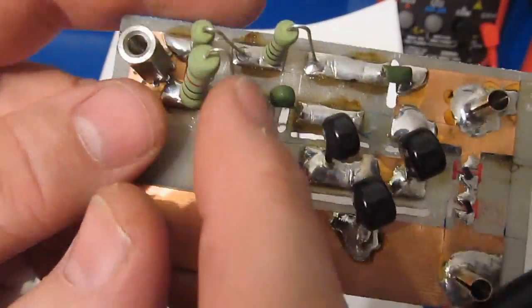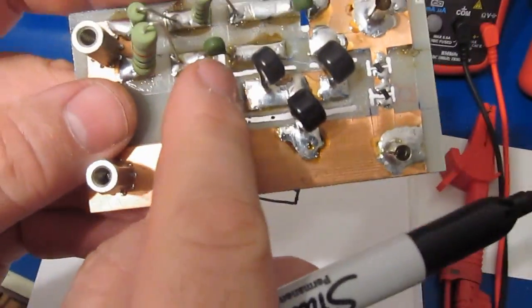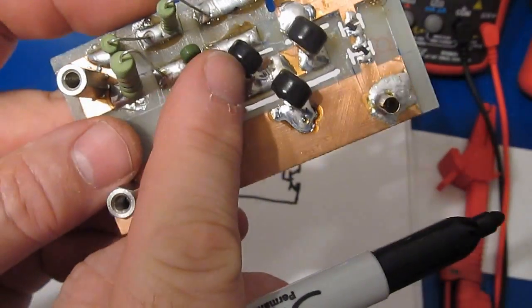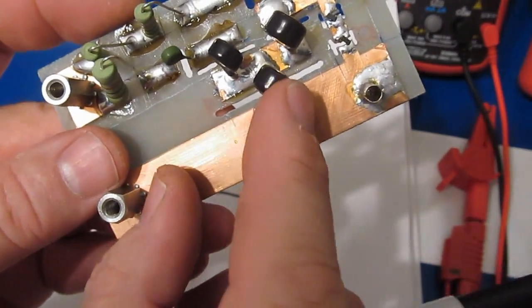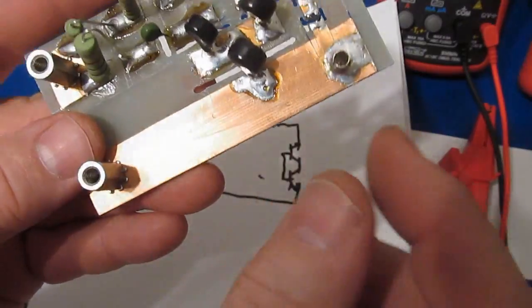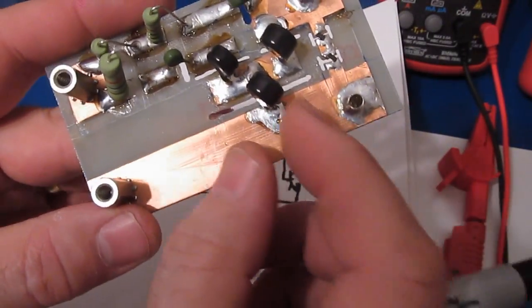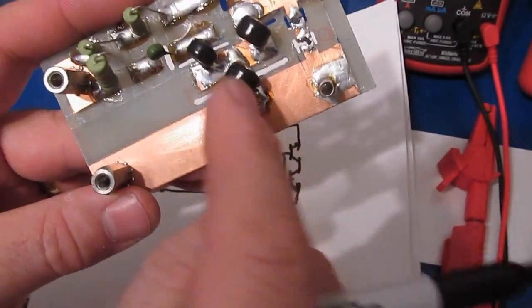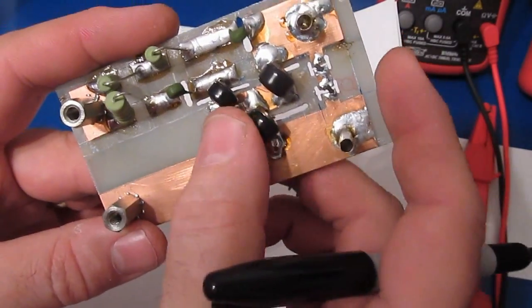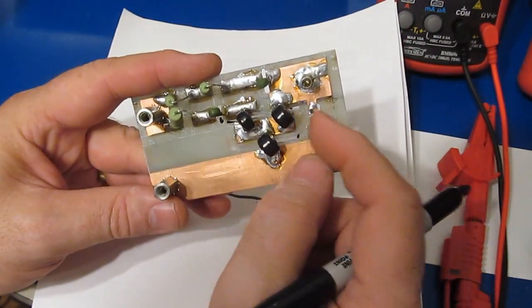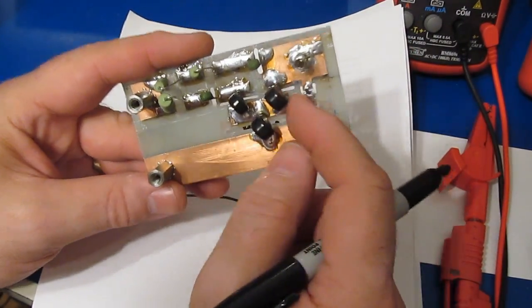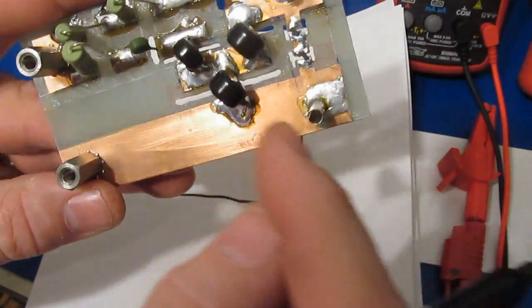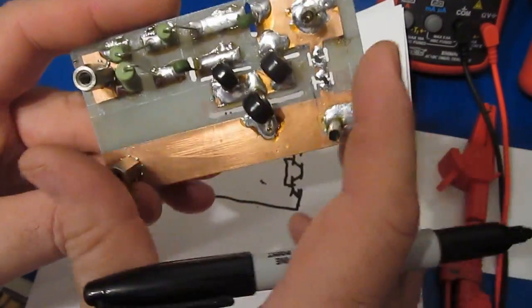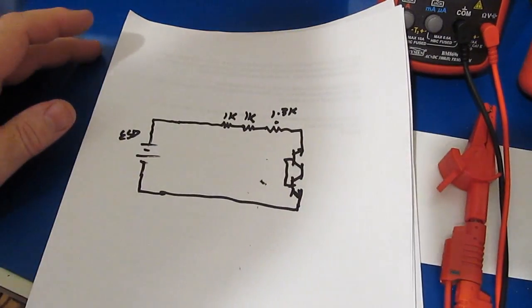Here's the PTC, and over here is our clamp, and then this is the return path. Of course, there are other parts on this board as well. There's another 1K and PTC that goes to this MOV, in series with another MOV, which returns to ground. These MOVs are rated for about 600 to 800 volts, so they won't break down at 1000 volts. It's the same for this MOV over here, straight across this PTC to ground, but that won't conduct at these low voltages.